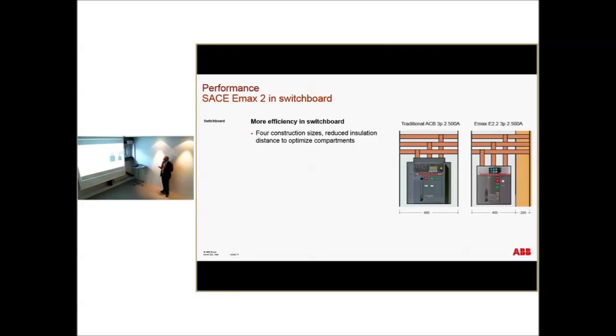And you see the distance between the bus bars doesn't differ. What is different is what is outside the bus bar. So the connection, you don't need to, again, squeeze the connection, otherwise the temperature rise will go to the moon. But you have a possibility to reduce cost. This is cost, this is cost, this is cost. The copper is cost, the metalwork is cost.